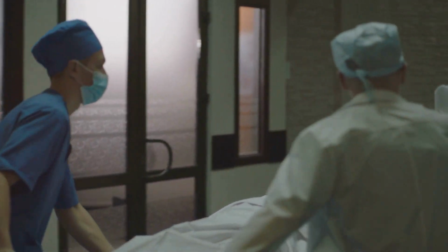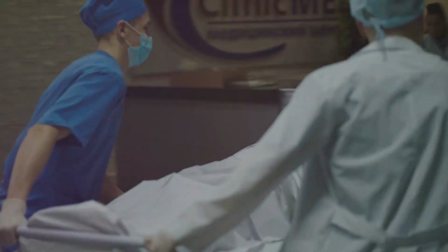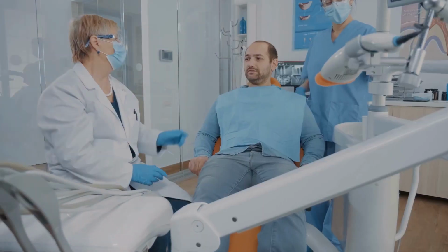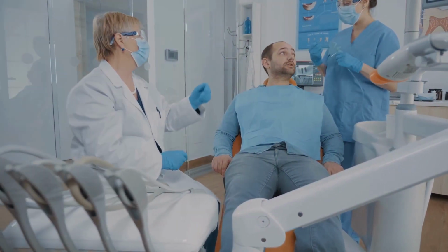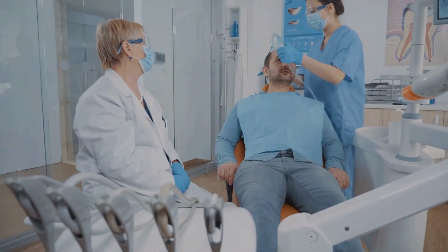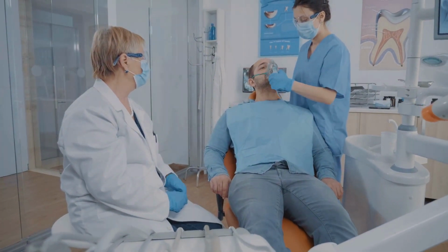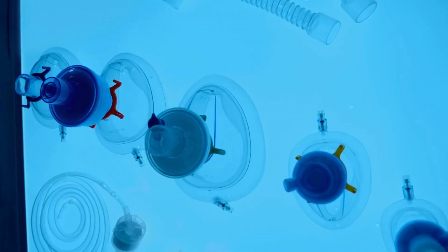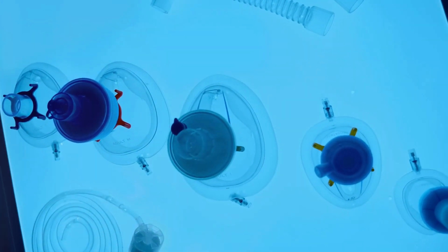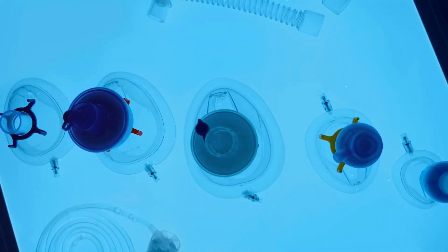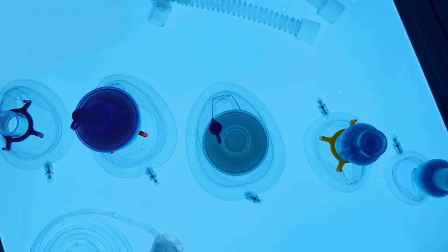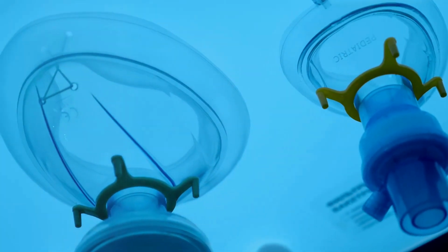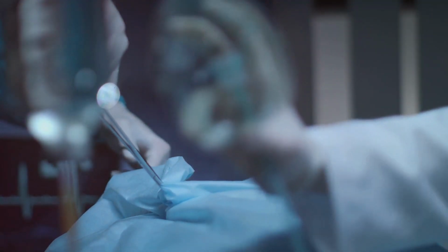These systems are responsible for delivering a carefully balanced mix of oxygen and anesthetic gases to the patient, while simultaneously removing carbon dioxide. The system comprises a series of tubes and valves that work in harmony to achieve this. Essentially, the breathing system is a conduit for the patient's breath. The oxygen and anesthetic gases are carried in one direction from the anesthesia machine to the patient, and the carbon dioxide is carried in the other direction, from the patient back to the machine. This two-way traffic is maintained by a system of valves which ensure that the gases flow in the correct direction.